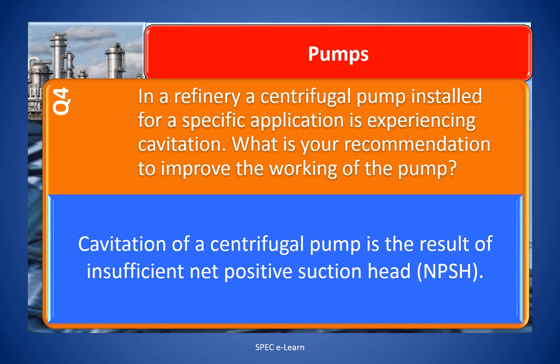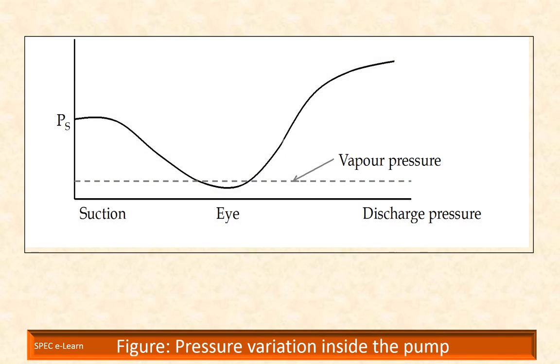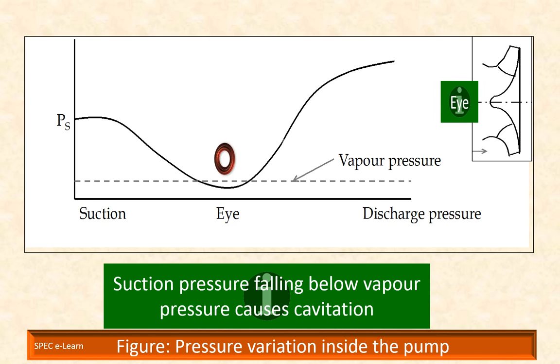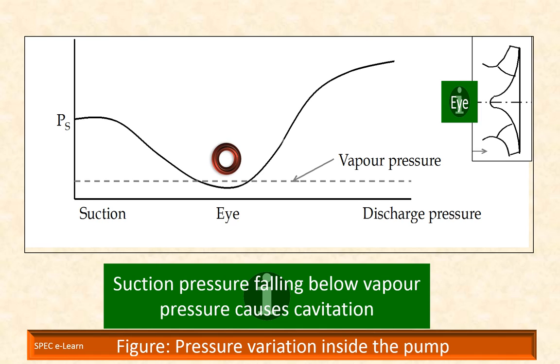Cavitation of a centrifugal pump is a result of insufficient net positive suction head (NPSH). Suction pressure falling below the vapor pressure causes cavitation. This figure illustrates how the pressure varies from the suction line to the eye of the impeller. As the liquid passes from suction to the eye of the impeller, the velocity increases and the pressure decreases. There are also pressure losses due to shock and turbulence as the liquid strikes the impeller. Centrifugal force of the impeller vanes further increases the velocity and decreases the pressure. All these pressure losses contribute to a drop in system pressure at the impeller eye, and bubble formation is a possibility if the net suction head is not sufficient.